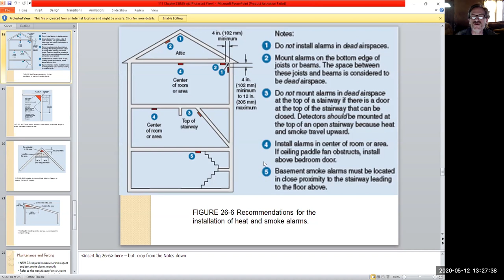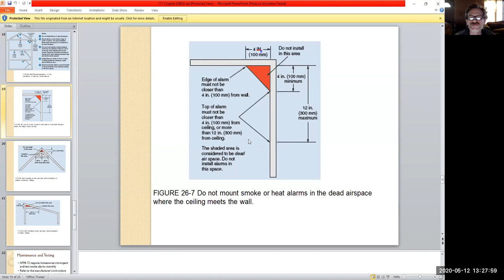It's not quite common sense, but if you think about how heat and smoke rise, it makes sense - these are the requirements. Here's the way to look at it: you don't want it in the corner. If you're on the wall, keep it at least the 4-inch minimum, no more than 12. If you're on the ceiling, no closer than 4 inches away from that edge.